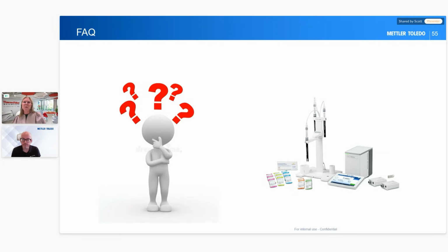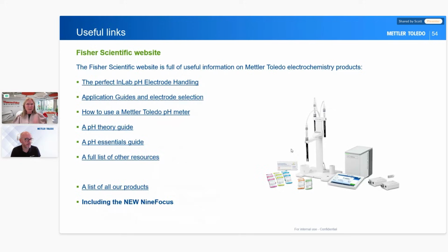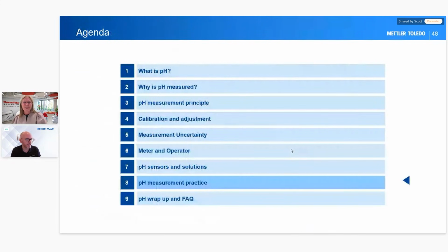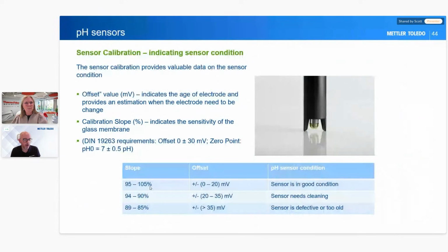And then we have from Sophia: the slope is fine, but the offset is getting higher. With a slope of 99.5% and an offset of minus 12.5 millivolts, is there something that can be done, or is it just to change electrodes? If I remember correctly, I don't think anything needs changing with that electrode. So if I go back, there we go. You can see a slope of 99.5 and an offset of minus 12.5 millivolts is absolutely perfect. The sensor's in good condition, so in that case, you don't need to change or do anything.